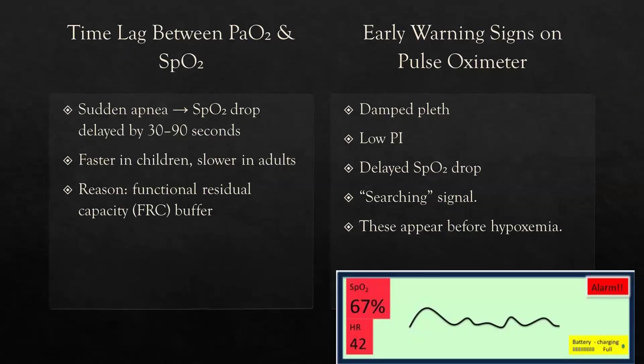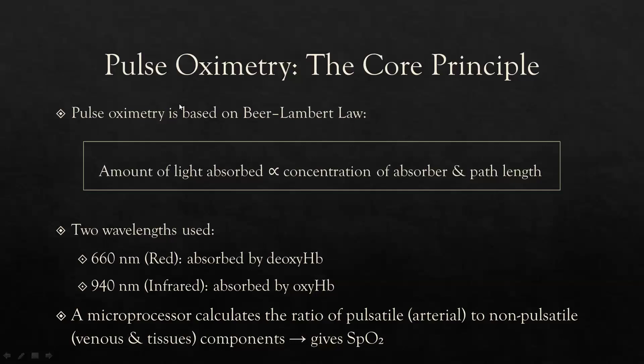Pulse oximetry, the core principle. Pulse oximetry is based on the Beer-Lambert's law, which means amount of light absorbed depends on the concentration of the absorber and the path it traverses. Two wavelengths of lights are used. One is 660 nanometer, which is absorbed by the deoxyhemoglobin, and 940 nanometer, which is absorbed by the oxyhemoglobin. Microprocessor calculates the ratio of pulsatile to non-pulsatile components, giving SpO2 reading on the monitors.